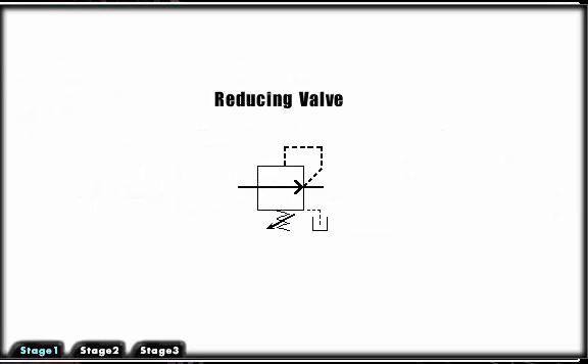A pressure reducing valve is a normally open pressure control valve used to limit pressure in one or more legs of a hydraulic circuit. Reduced pressure results in a reduced force being generated.